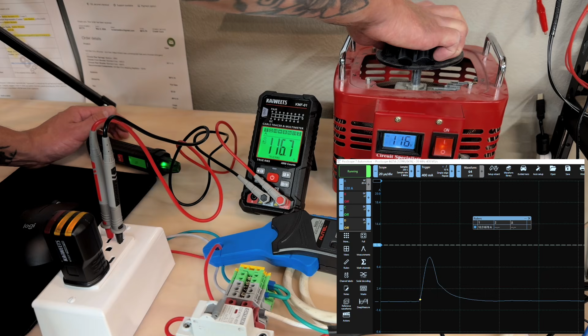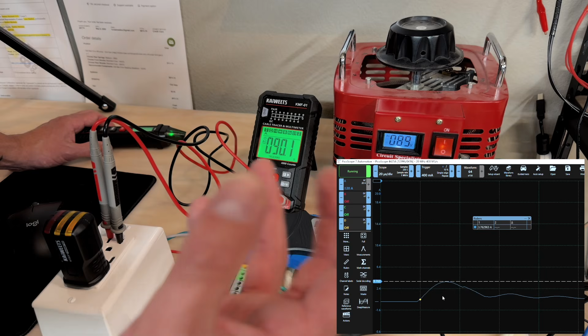We can look on the scope at our current along with our voltage, and watch how it doesn't take much of a voltage drop to drop that signal down. Let's bring it down — I believe the floor they set for this device is no less than 90 volts, because at 90 volts our signal is diminished to 3.7 amps. With all the electrical noise going on in your panel, you're going to have a really hard time tracing circuits. I just thought that was really cool and fun and wanted to share it with you all.